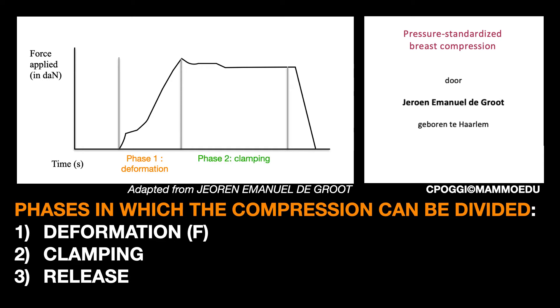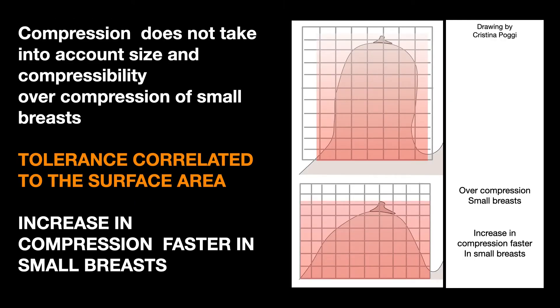Second, the immobilisation or clamping phase, in which the paddle is held stationary — the purpose is to lock the breast. And then the last phase: the release. As we have seen in the first lesson, the effect of the applied force is not always the same; it depends on the characteristics of the breast. Compression does not take into account the breast size and compressibility. Women with small breasts are often over-compressed — they perceive a compression force up to three times higher than women with larger breasts. The tolerance is related to the surface area, and in smaller breasts the increase in compression force is felt much faster, whereas with larger breasts the force is distributed over a larger area.